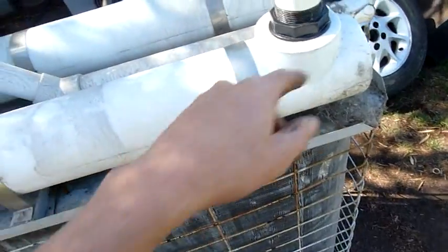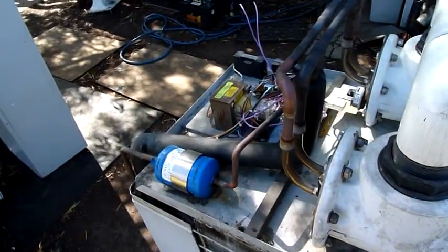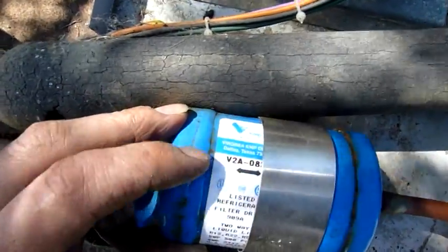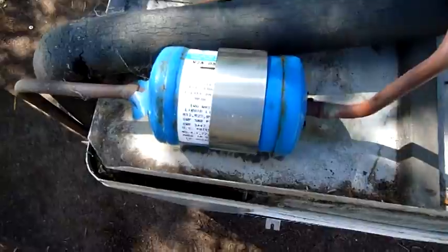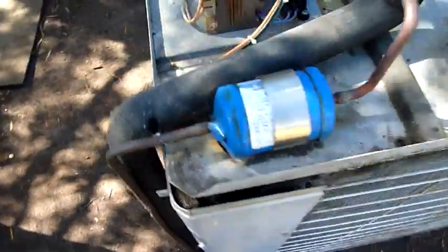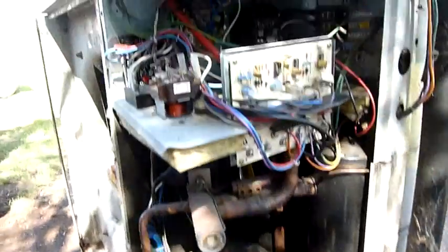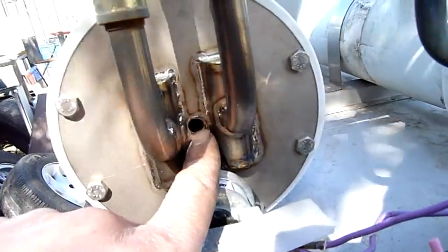Now that the outer shroud's off, this whole thing's loose. It's got a very old Virginia KMP filter dryer — Bi-Flow, liquid dryer. These things can heat and cool, but these are only ever used for cooling. And that's where the temperature sensor goes, down inside there.